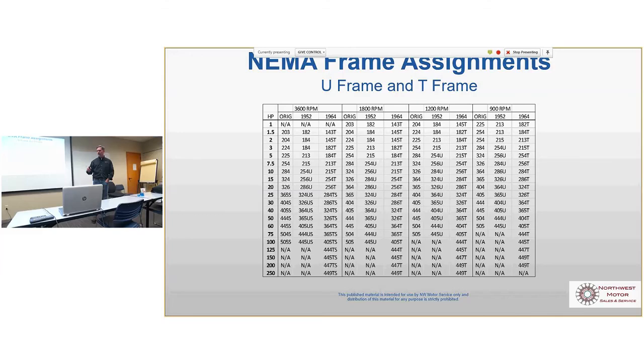The last thing about frame sizes: a lot of guys, and I wondered this at first, ask what those numbers mean. Is there any meaning to them? And there actually is. The first 2 digits divided by 4 is the shaft height. I'll pick an easy one because I'm stupid. If we look at a 449T frame motor, that's an 11-inch shaft height. So that dimension you're able to figure out. If you're looking at a motor in the field and you're not sure what your measurement is, because it's always hard to figure out with a tape, with a coupling guard or a pulley or something in service, that number divided by 4 is your shaft height, which helps steer you to the right frame or right motor if you're not quite sure what you're looking at. The last number doesn't mean anything. Yeah, that works all the way through, even down to 3.5, all the way to the big ones.